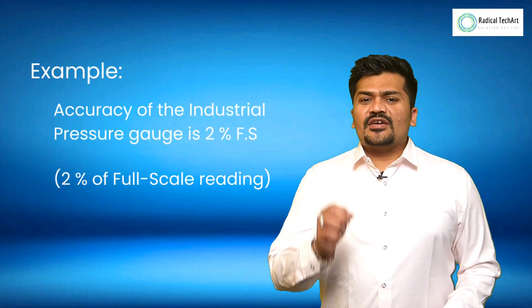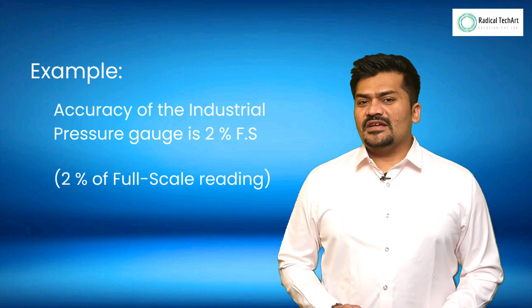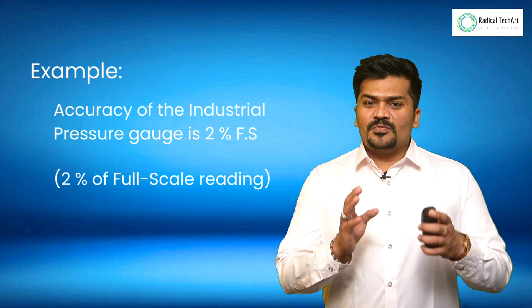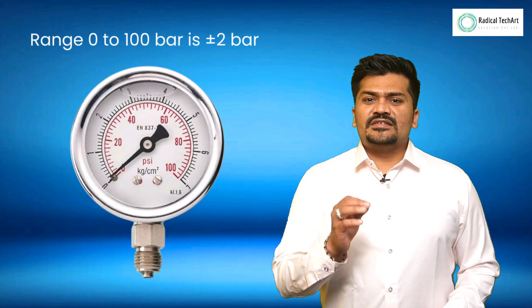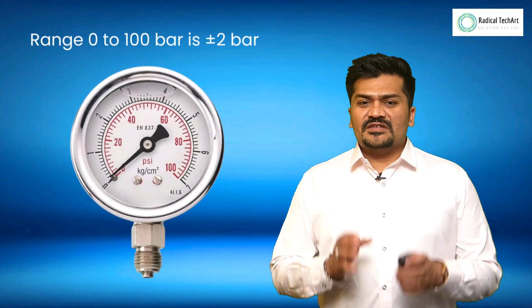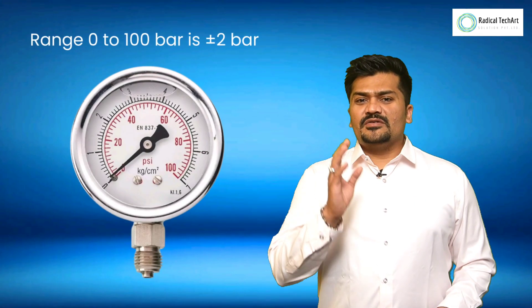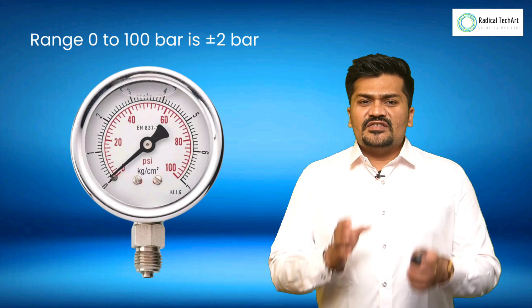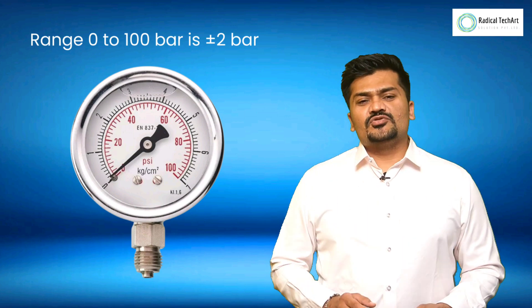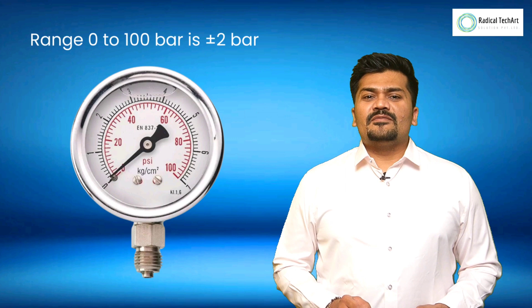Let's take one example: the accuracy of an industrial pressure gauge is 2% of full span. Consider a pressure gauge with a range of 0 to 100 bar — the accuracy is plus or minus 2 bar, meaning any measured reading can vary within plus or minus 2 bar.